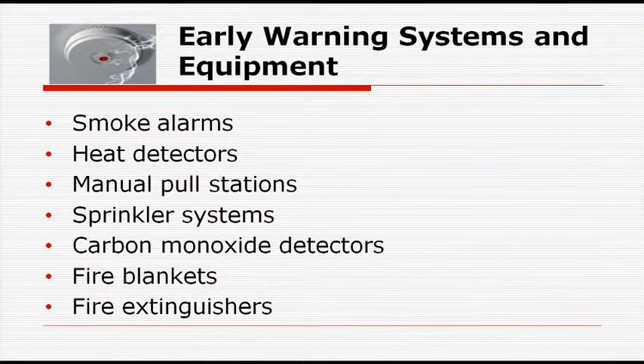Back in the day, what used to happen is people would have smoke alarms in their kitchens, and when they burned their microwave popcorn or something, the smoke alarm would go off. Well, now we put a heat detector in the kitchen, and the alarm will not go off unless it reaches a certain temperature, so you can burn that microwave popcorn and be okay. The heat detector will be aware of that. The other locations for them would be like a furnace room or a laundry room or, say, an attached garage. Care and maintenance for heat detectors is exactly the same as for smoke detectors. If there's been a fire, it needs to be checked within 10 days, and if it's malfunctioning, replaced within 5.